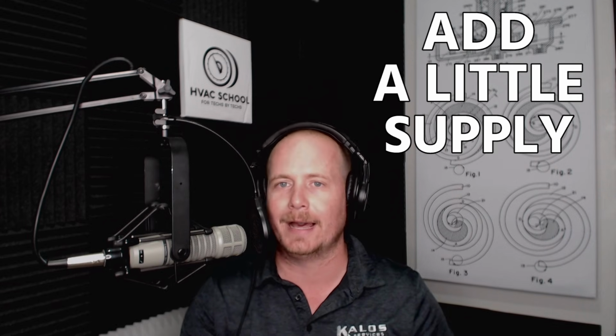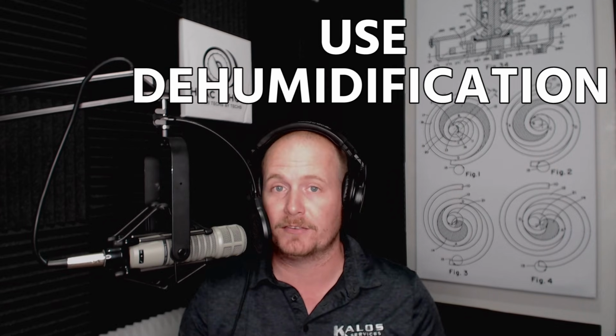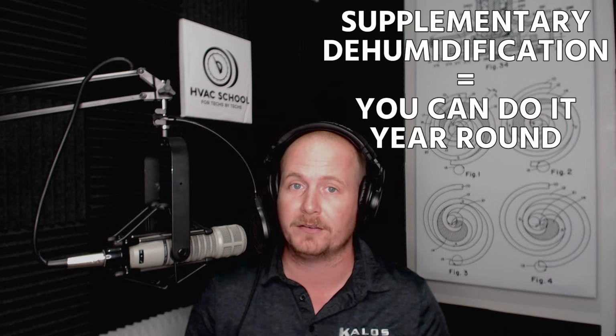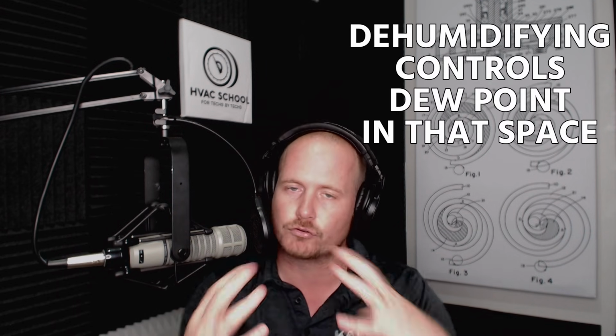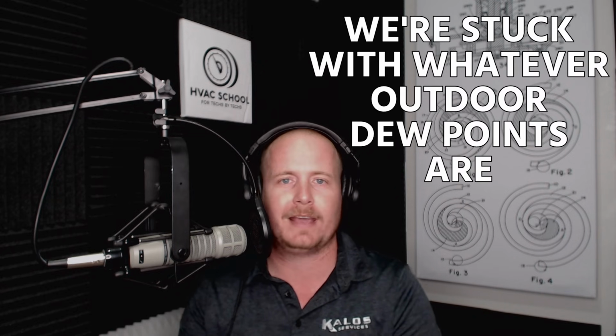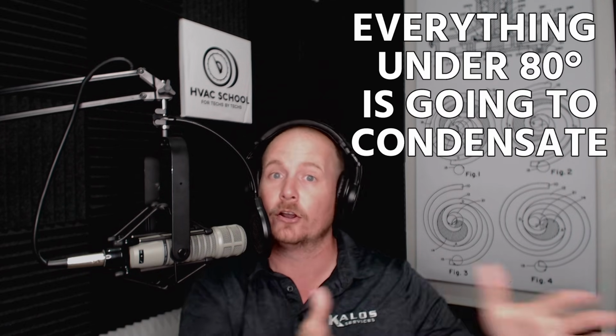Add a little return, add a little supply. Better yet, use dehumidification. I'm a big fan of supplementary dehumidification because then you can do it year round, but in some way dehumidify and control the dew point in that space. Just remember that when we ventilate, we're stuck with whatever the outdoor dew points are. And in Florida, we often have outdoor dew points that can reach 80 degrees. That's a very high dew point. That means anything under 80 is going to condensate. And so you really want to think about what your solution is going to be.